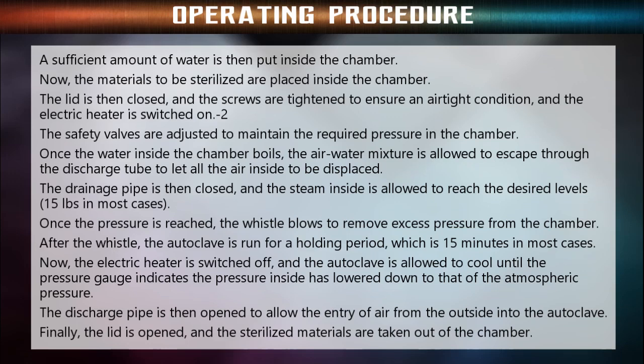The safety valves are adjusted to maintain the required pressure in the chamber. Once the water inside the chamber boils, the air-water mixture is allowed to escape through the discharge tube to let all the air inside be displaced. The complete displacement can be ensured once the water bubbles cease to come out from the pipe. The drainage pipe is then closed and the steam inside is allowed to reach the desired level. Once the pressure is reached, the whistle blows to remove excess pressure from the chamber. After the whistle, the autoclave is run for a holding period which is 15 minutes in most cases.